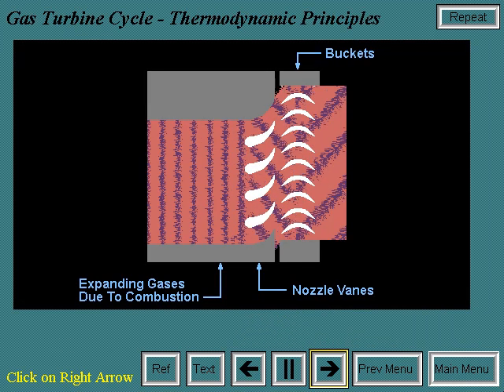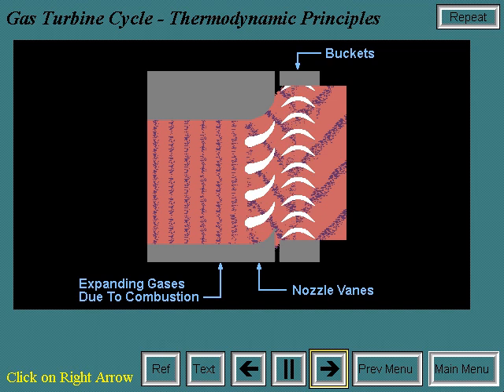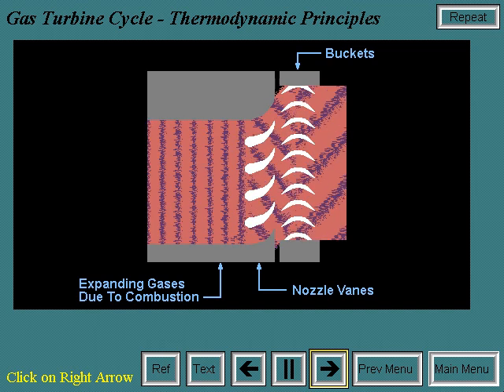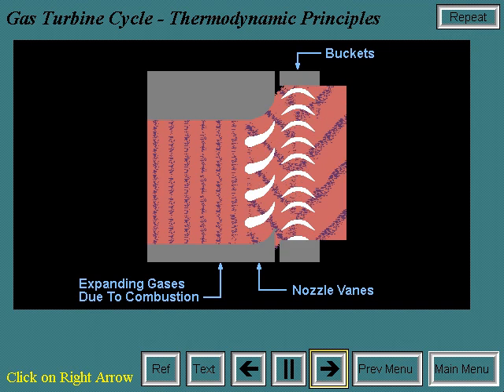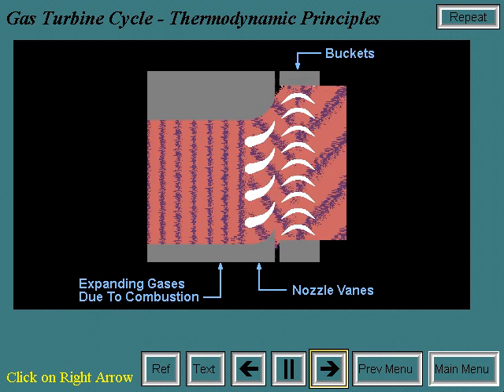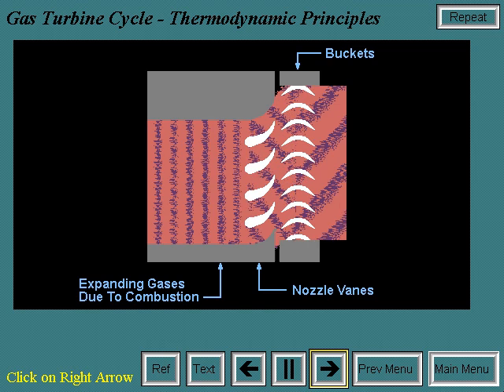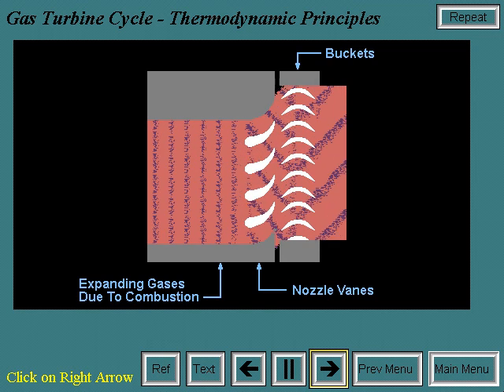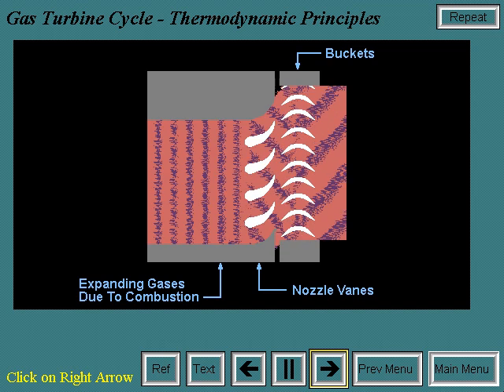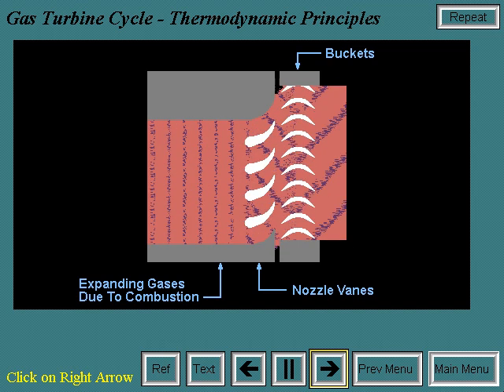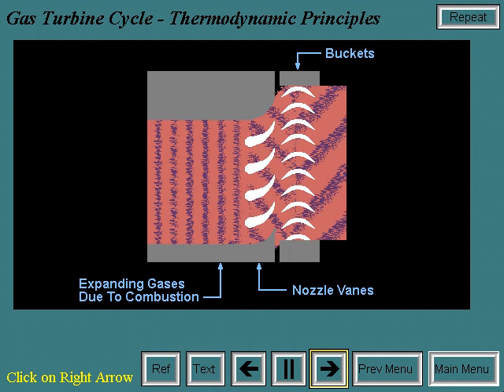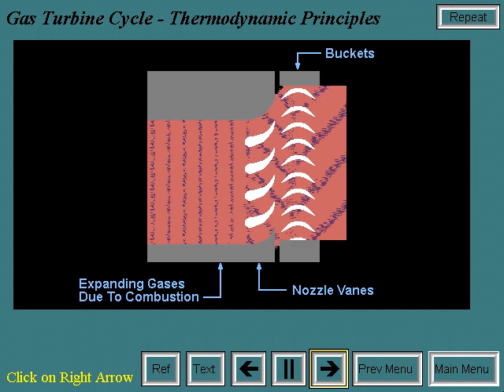The conversion of work in the turbine actually takes place in two steps. In the nozzle section of the turbine, the hot gases are expanded, and a portion of the thermal energy is converted into kinetic energy. In the subsequent bucket section of the turbine, a portion of the kinetic energy is transferred to the rotating buckets and converted to work. Typically, more than 50% of the work developed by the turbine section is used to power the axial flow compressor.